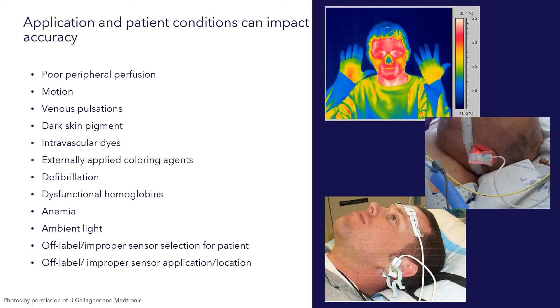Dysfunctional hemoglobins, as mentioned earlier, are those types of hemoglobins where the pulse oximeter may become confused with saturation of oxygen with hemoglobin versus saturation of hemoglobin with carbon monoxide. So carboxyhemoglobin can create a falsely elevated oxygen saturation relative to the actual oxygen saturation of the hemoglobin. It is only in measuring on a co-oximeter that we can truly know if the oxygen saturation is accurate.